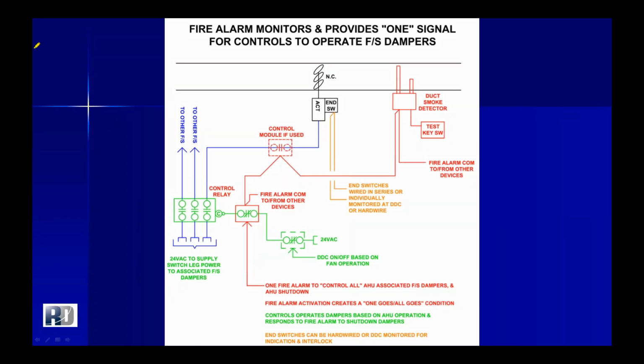So what we've created here is just kind of a little diagrammatic sketch to illustrate what's going on. We would have that duct detector sitting on the fire alarm network, and there would typically be a control module that could be activating that individual duct or fire smoke damper, but doesn't necessarily have to be the case. The more important module is the one that's on the center left, which is the fire alarm control module. Oftentimes in specifications around here in Wisconsin, and it's actually in code, it says the control module will be located within 5 feet of a temperature control panel. This device here can actually be used to energize, de-energize a whole bank of powered fire smoke dampers.